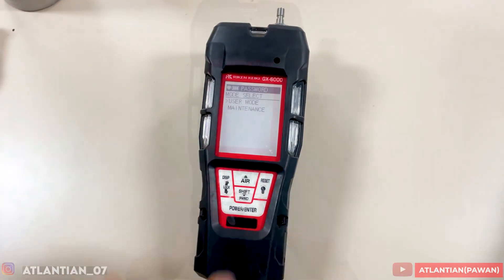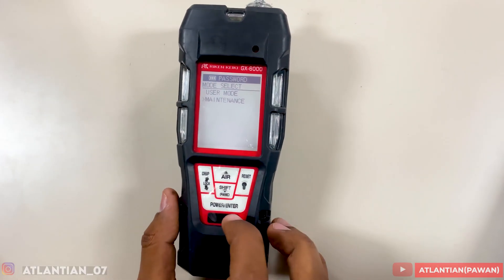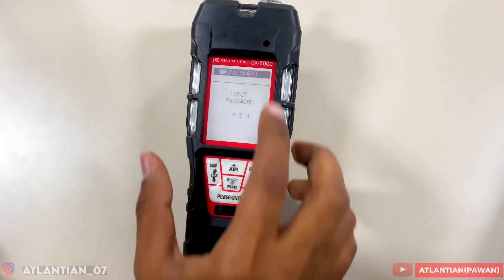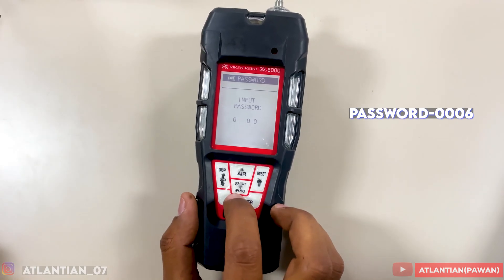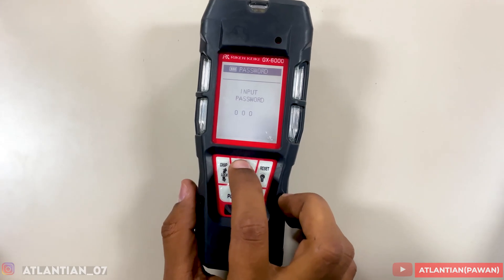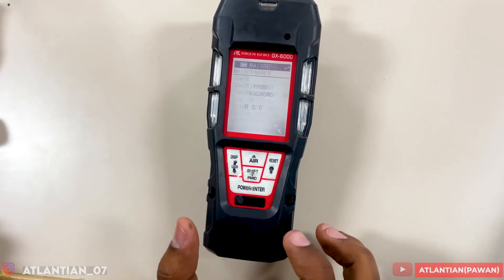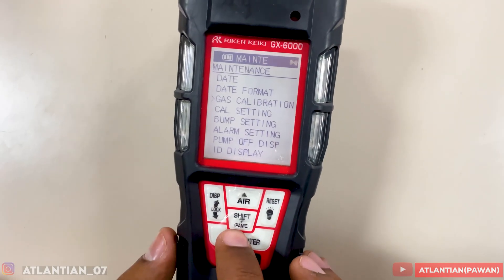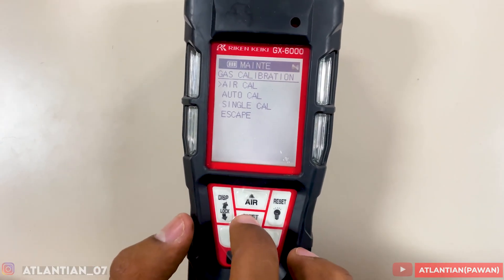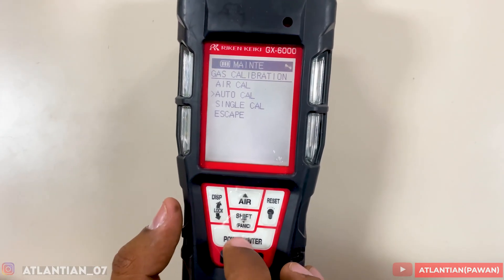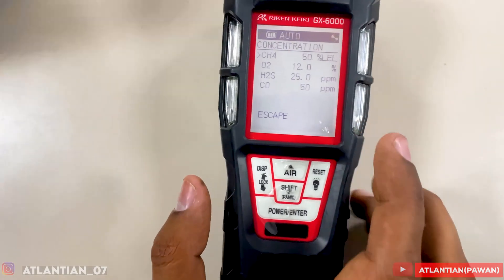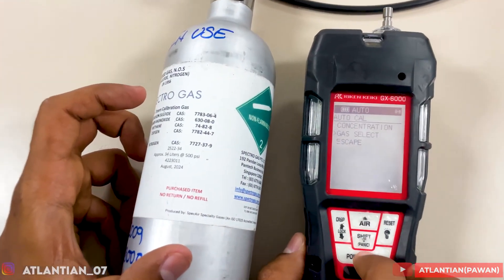After pressing those three buttons together, you can enter into Maintenance mode. The password for the GX-6000 is 0-0-6. Enter, Enter, Enter to input the password. This brings up the Gas Calibration menu — press Enter. You can choose Air Calibration, Auto Calibration, or Single Calibration. Select Auto Calibration and press Enter.